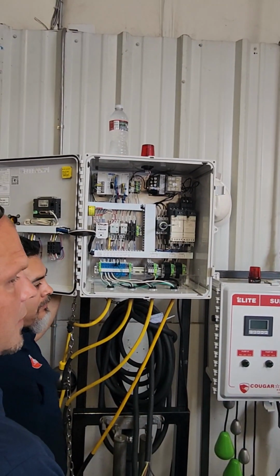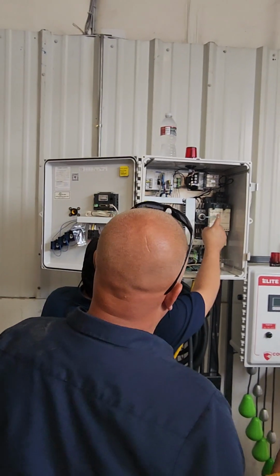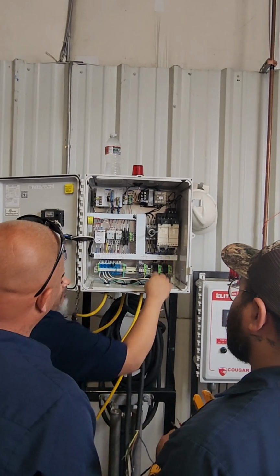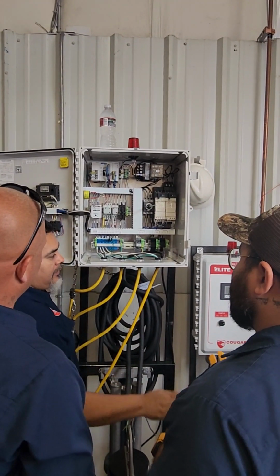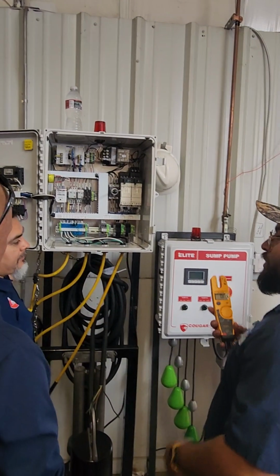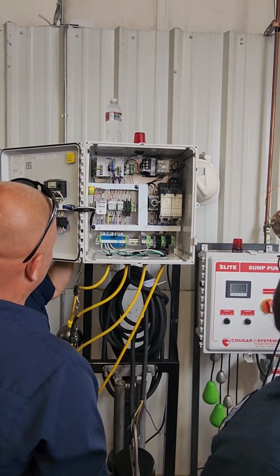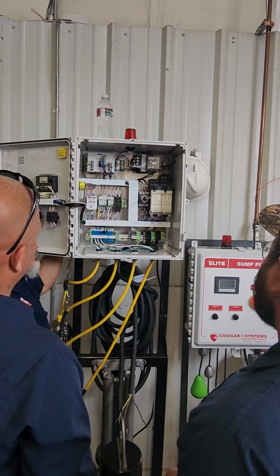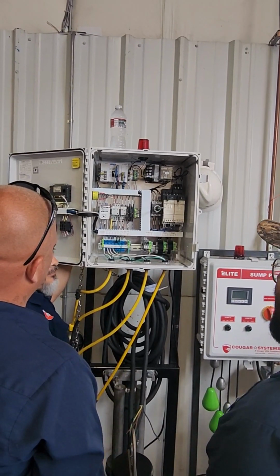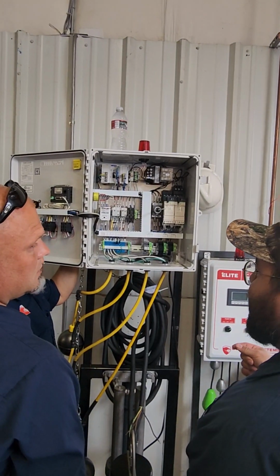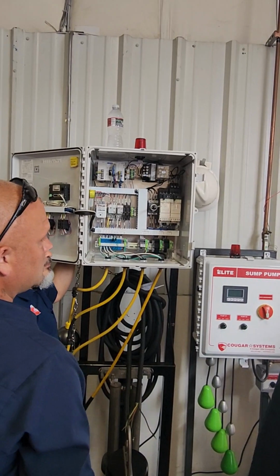It has to be locked up. In other words, if you have this set at 10, and right here you're reading 30, that's too much, way beyond, and that's why it's tripping. Then flip the lead, put it on reverse, trying to check it. Especially if you're getting that delayed flip, right? Yeah, if you're getting that delayed flip, that means the motor's locked.